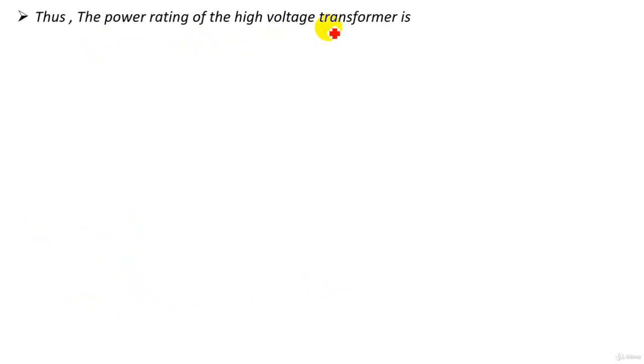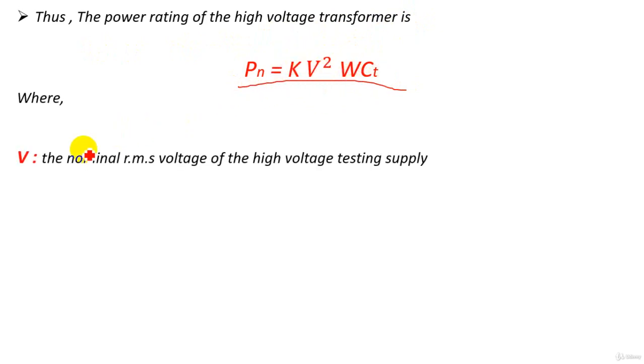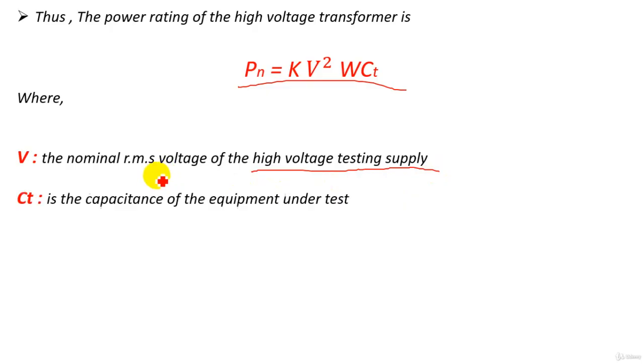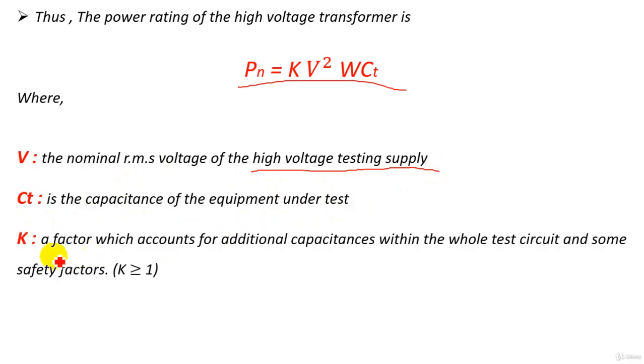Thus, the power rating of high voltage transformer, after taking into consideration the compensation factor, Pn equals V square omega Ct times K, where V is the nominal RMS voltage of the high voltage testing supply, so high voltage side of our transformer, while Ct is the capacitance of the equipment under test, and K is a factor or safety factor for additional capacitances within the whole circuit and some safety factors, and K should be bigger than 1.